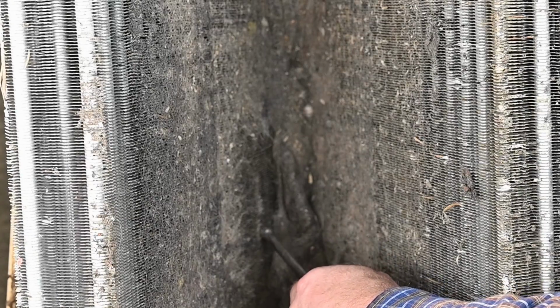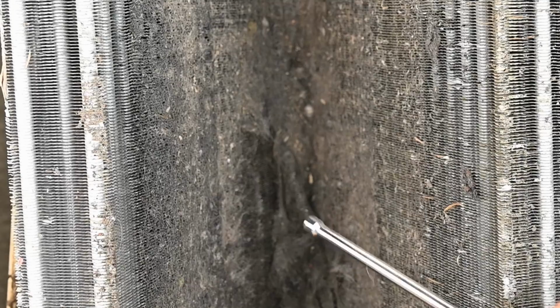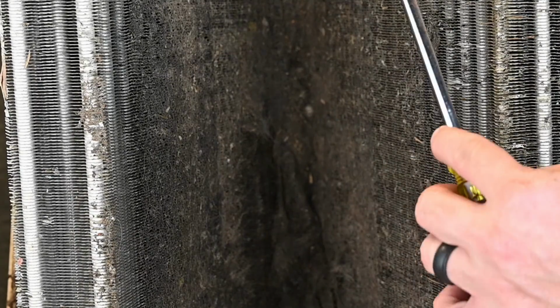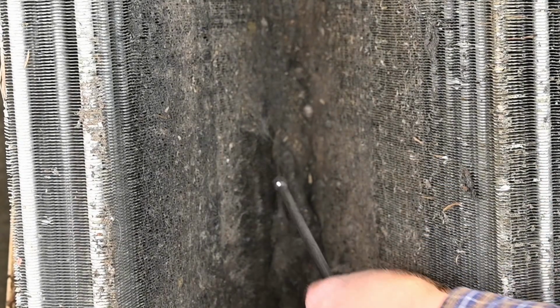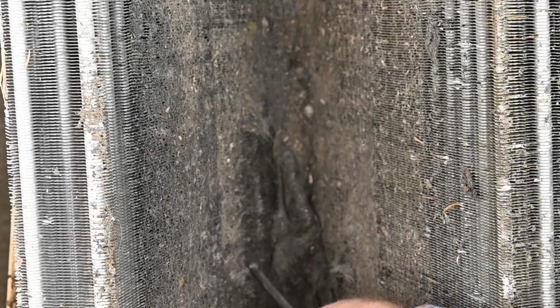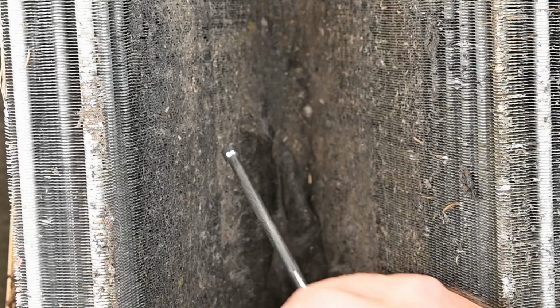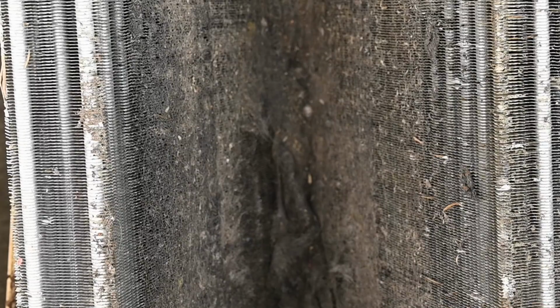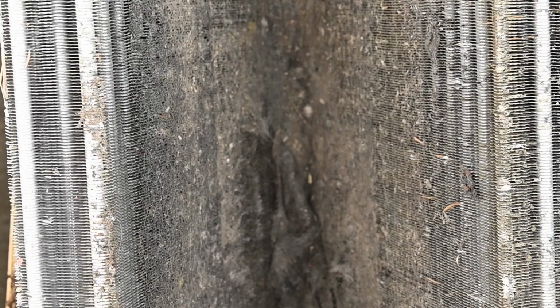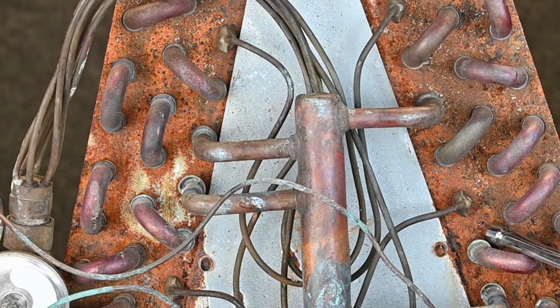But inside of here, we see behind all this dirt, this evaporator coil is damaged. So even if we were to clean this professionally, because it's been damaged, as we put it back into service, and as bad as this is, it very well could be corroded. The water could be dripping off of this. So before we quote an evaporator coil clean, we want to also take a look at what's the condition of the metal. And if we turn this coil back over the other way, we can see there's a significant amount of rust. Now, rust doesn't mean it's leaking, but it is another point we want to look at.